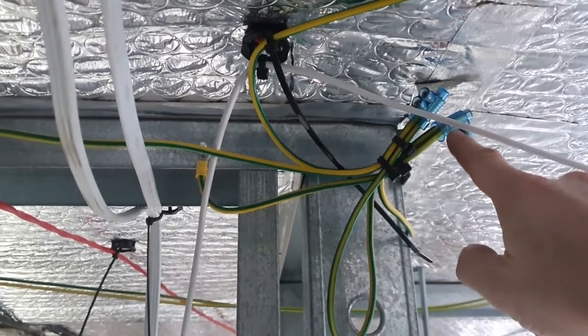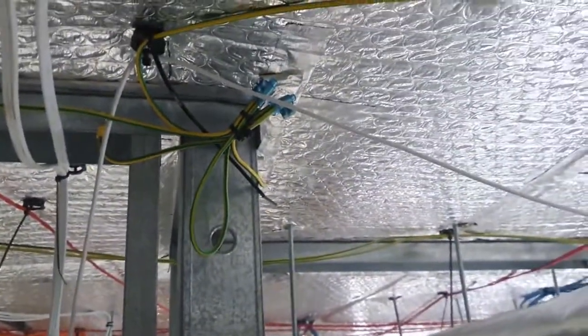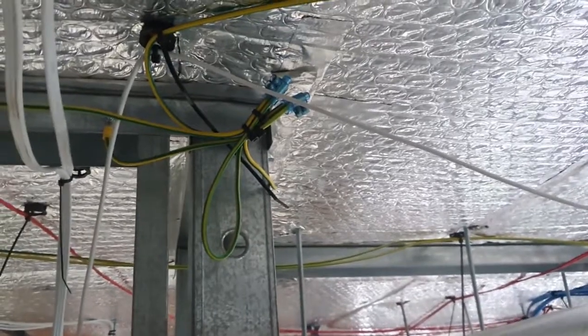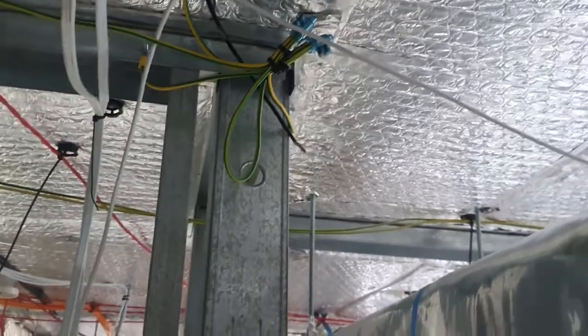So there's a feed, a tail that way, and then a tail to this connector. And from this connector, I've got two tails. One picks up the top plate there, and one gets the one around the corner there. So I'm covered continuity-wise with this earthing thing. So that's in the standard AS3003. So I must abide by it. Put it down, we go.